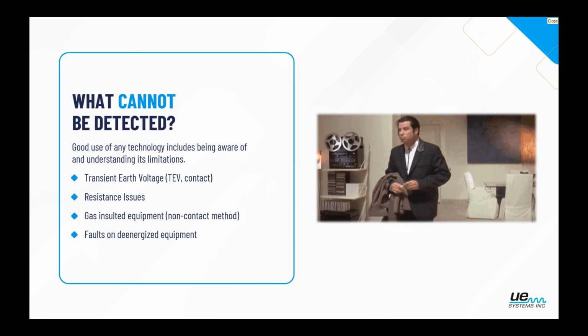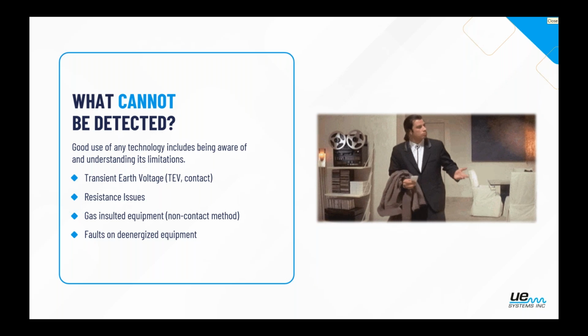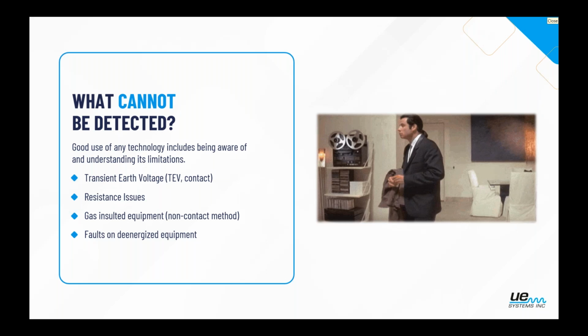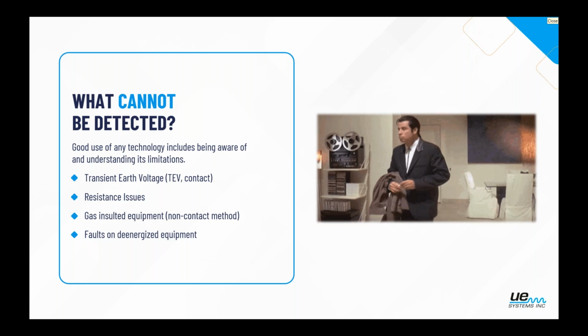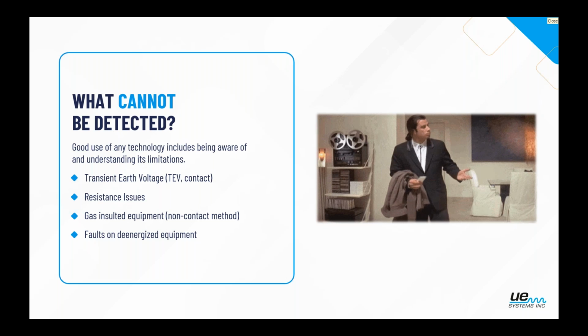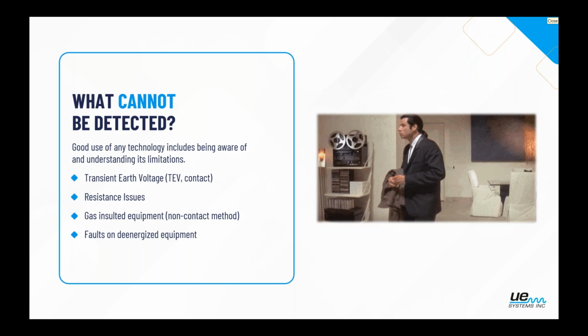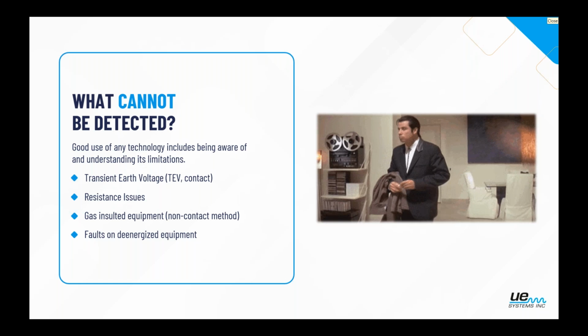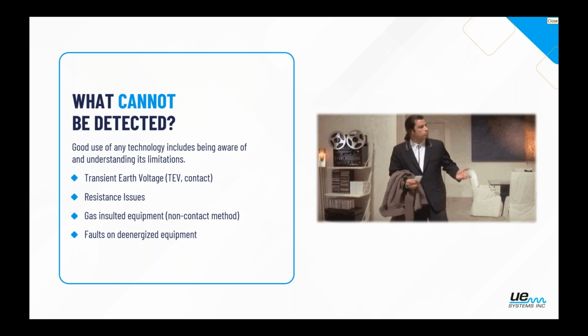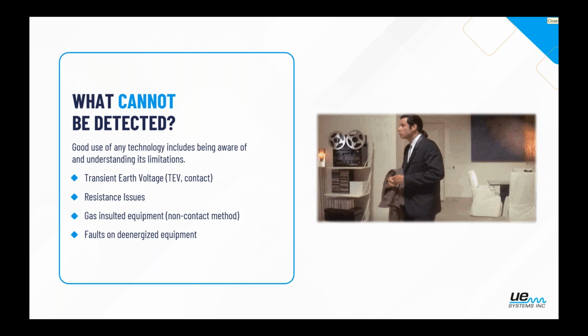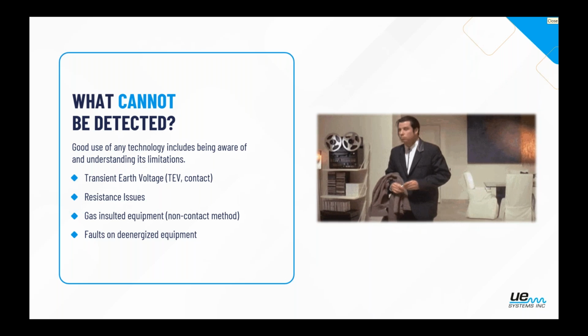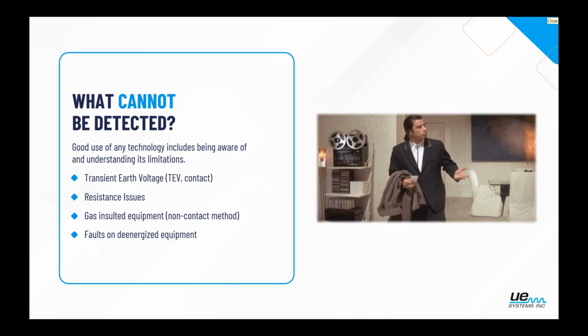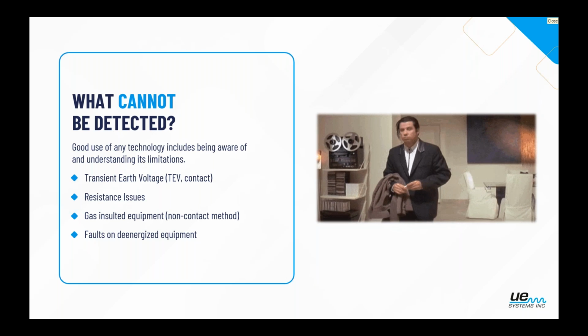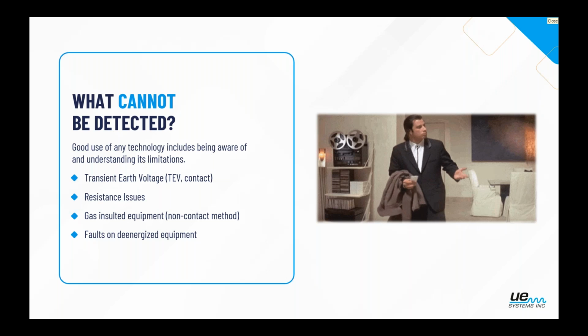And then the last one, as I mentioned earlier, we cannot find partial discharge issues if the equipment is not energized. So it's always a critical thing. Be aware of what is and is not energized when you're doing these inspections. For those of you that are not doing your inspections in-house and are having a service provider come in, make sure that they are fully aware of what is and is not energized, just as you would with an infrared scan, with things on the heaviest load possible. You'd want to make sure as much equipment is energized so they can inspect everything at once.